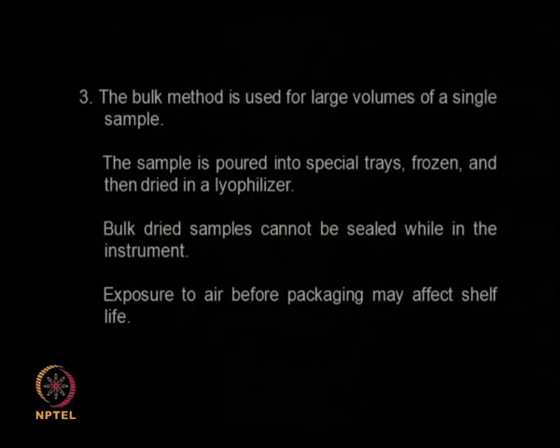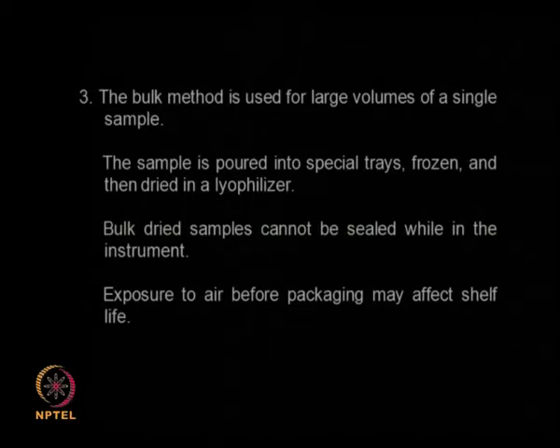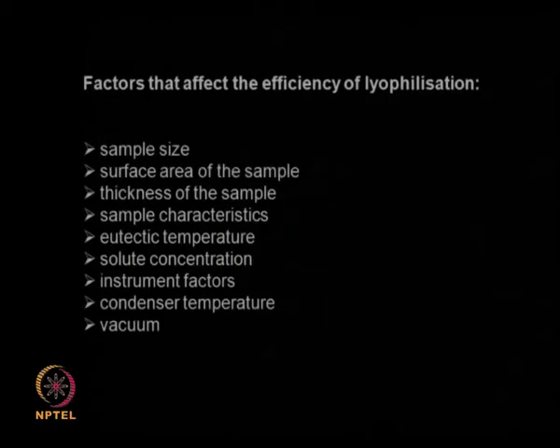For not exposing the material to the outside atmosphere, the best method is manifold drying or vial drying — you take samples in hundreds of vials, freeze them, connect to a manifold, apply vacuum, slightly heat up, remove all moisture, and then seal the vials. In the tray type you can handle large quantities of material, but some amount of exposure after lyophilization is inevitable.